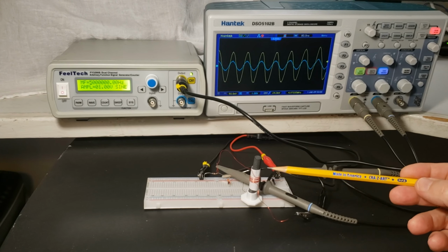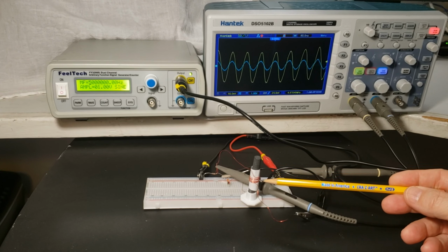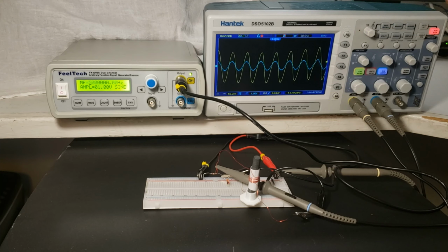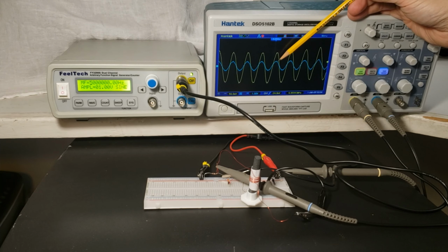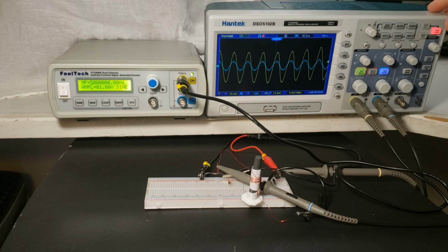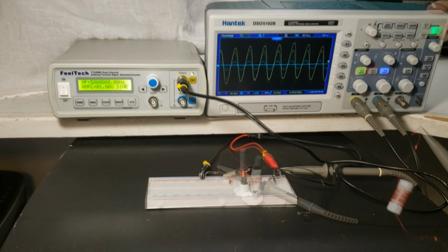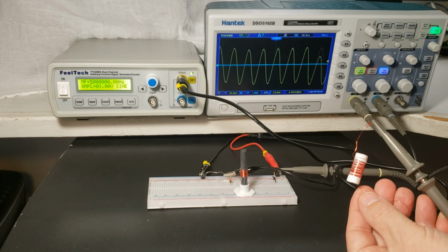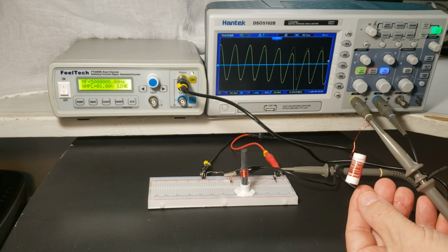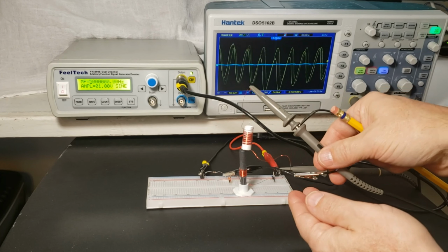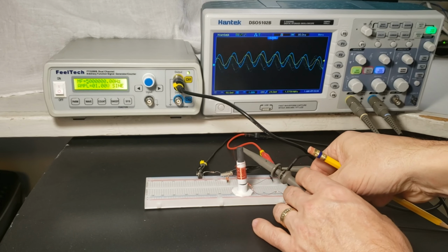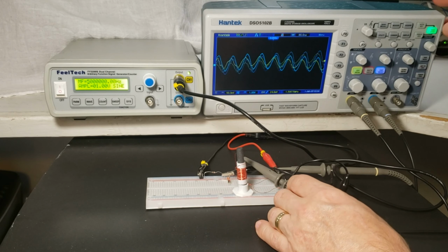You can see that because the secondary has half the number of turns, it produces almost half of the current in the secondary. We can do the same thing in the opposite direction with this. This is a 40-turn secondary, and if we drop this over the top of our primary, you notice that the load is really high.